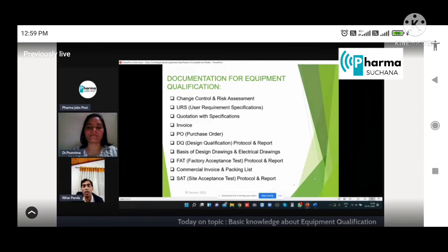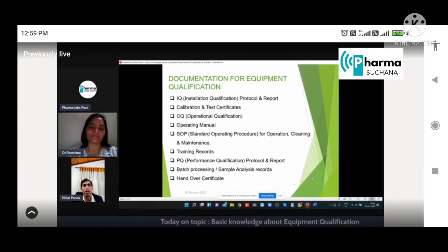What are the different boxes received? How many packs are received? How much quantity is received? Whether they are received as per the requirement, as per the packing list, whether any damage is there. Those things can be checked during SAT. After SAT, you can ask the service engineer, the vendor, the manufacturer. They will send the service engineer for the installation qualification, IQ.